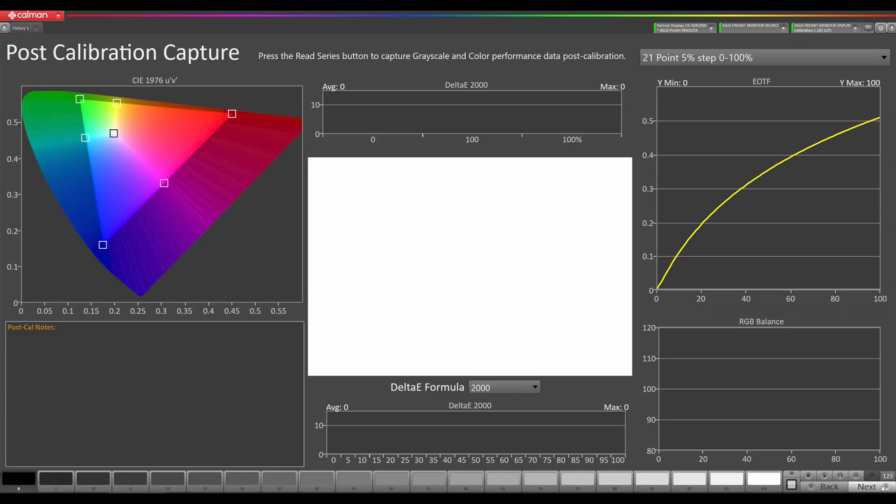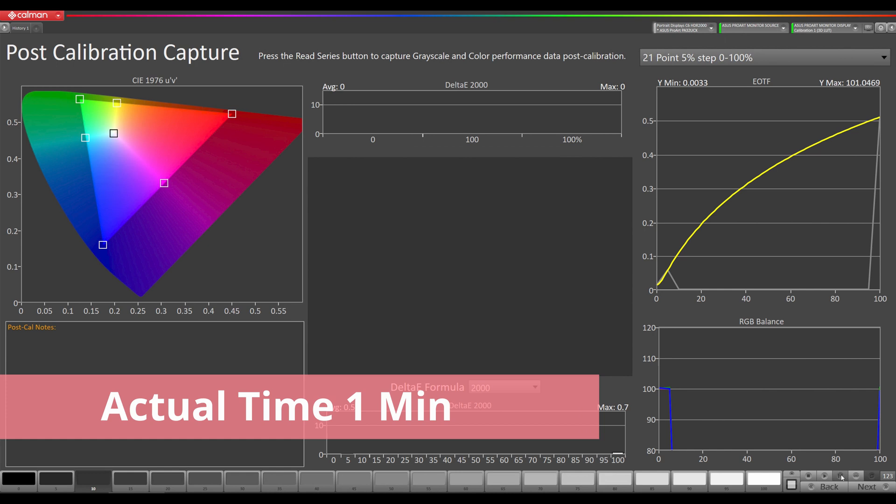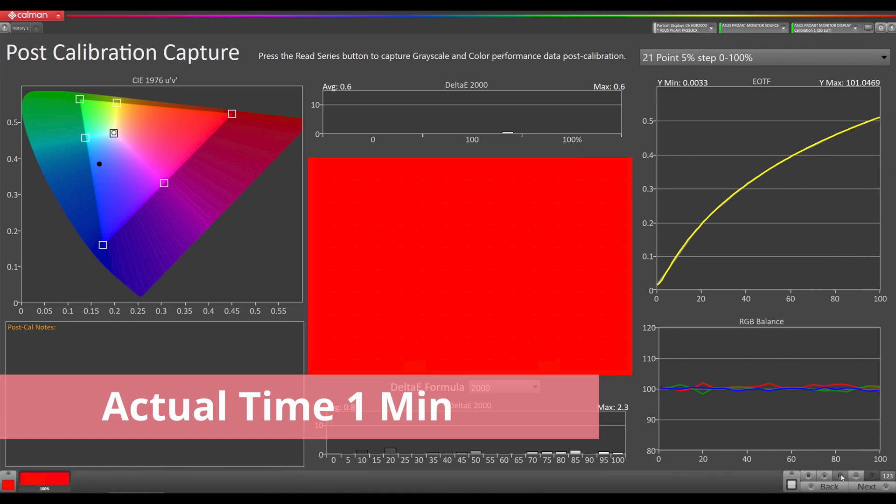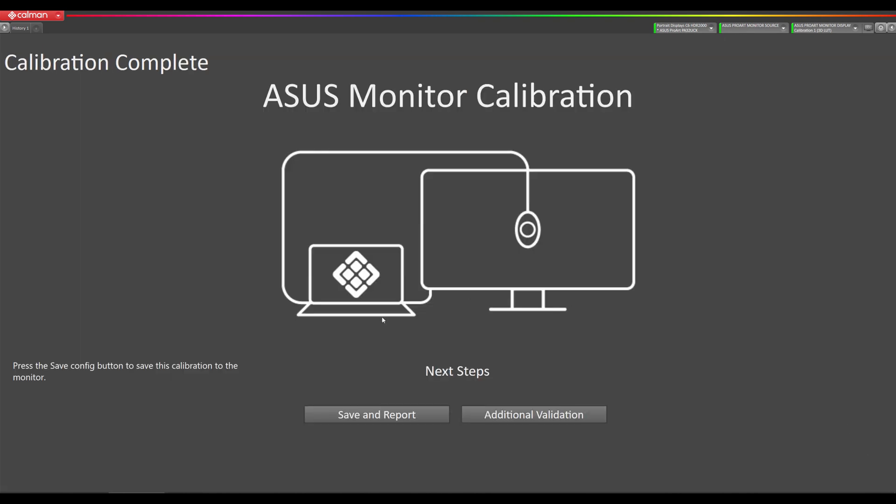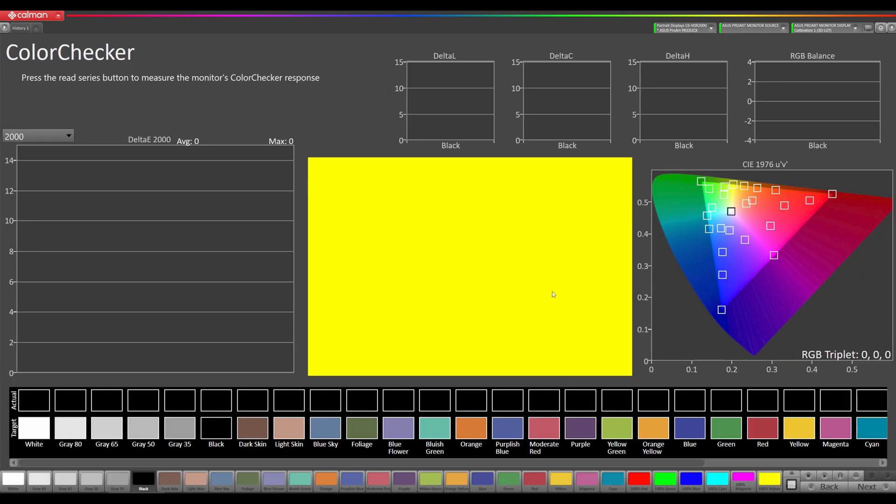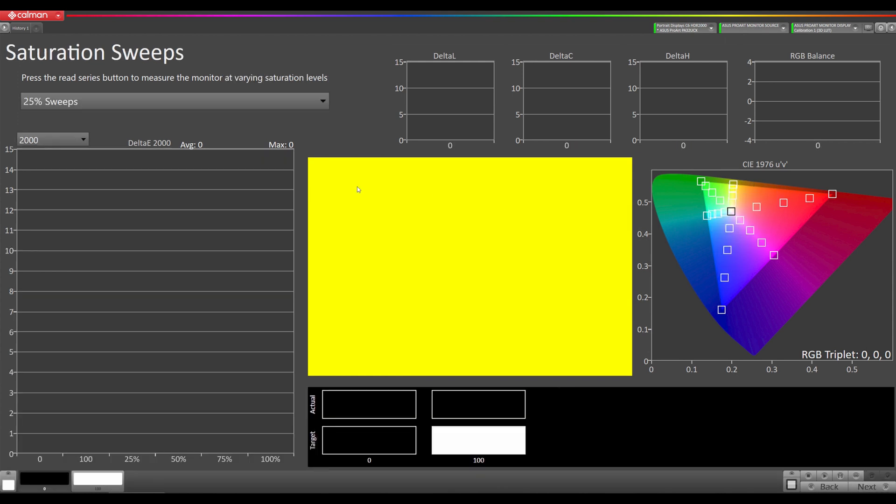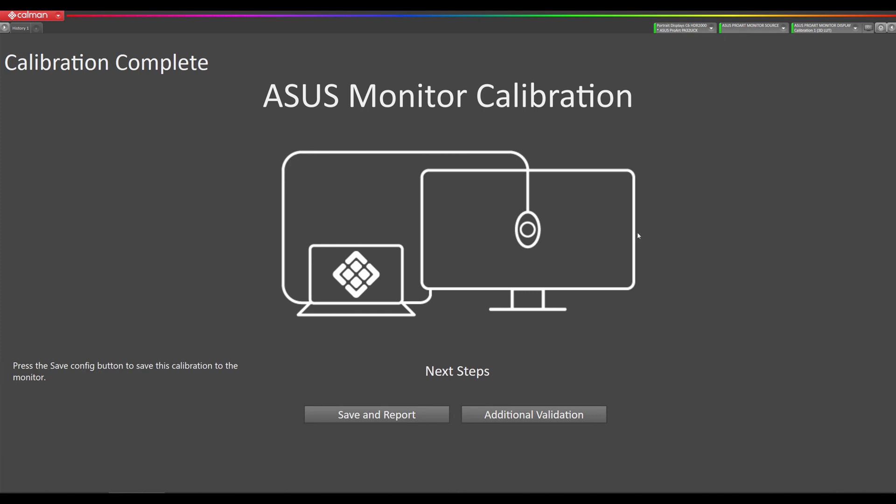Next step is our post calibration measurements. So we're going to hit read series here. Post calibration measurements are complete. Now we can save and generate a report, or you can do additional validation where you can do the color checker or saturation sweeps, and then it will take us back to our report.